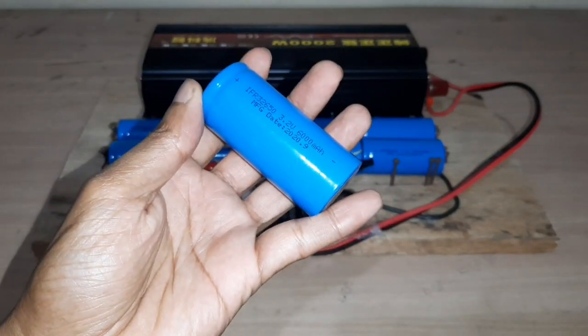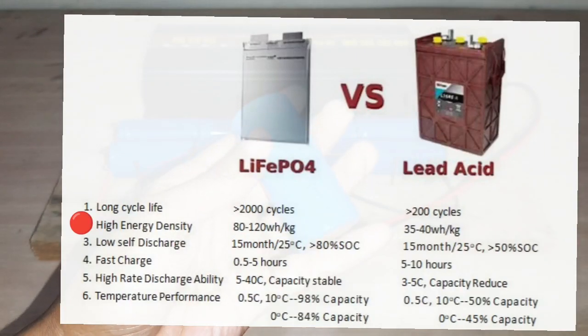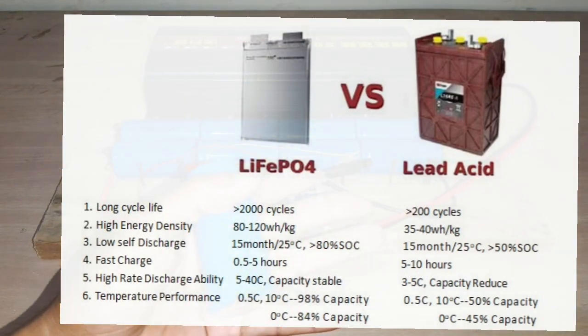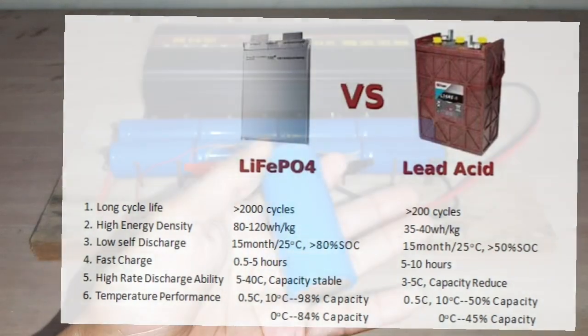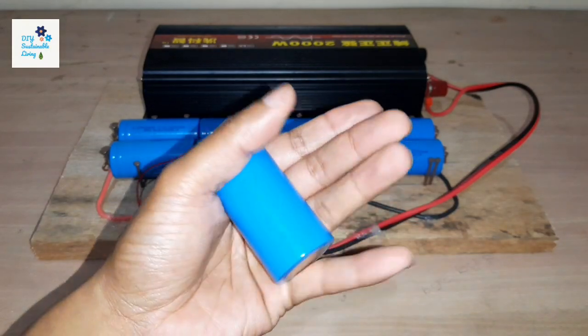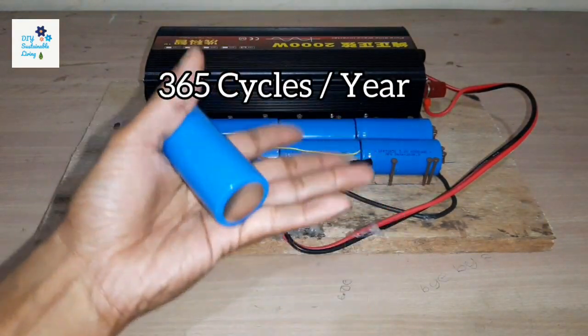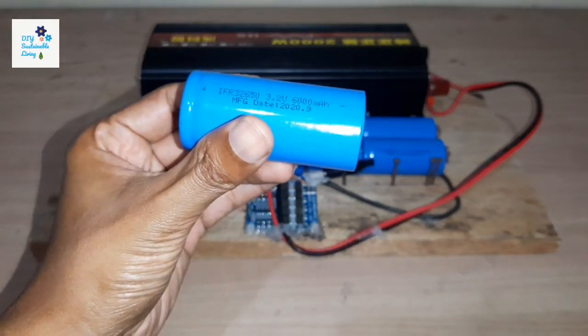Currently the best batteries for solar power storage are lithium batteries, specifically lithium iron phosphate. Lithium batteries in general have a higher energy density and are capable of storing much more energy per kilogram than the common deep cycle lead acid battery. The life cycles for lithium iron phosphate at 80% depth of discharge is 2,000 cycles, whereas lead acid batteries you can barely get 300. Even for lithium ion cells it comes to around 800 cycles, with the best batteries reaching around a thousand. In solar applications you will have daily cycling — charged during the daytime and discharged at night — so for one year you go through 365 cycles. Basically a lead acid battery will last about one year, while lithium iron phosphate should last five years.